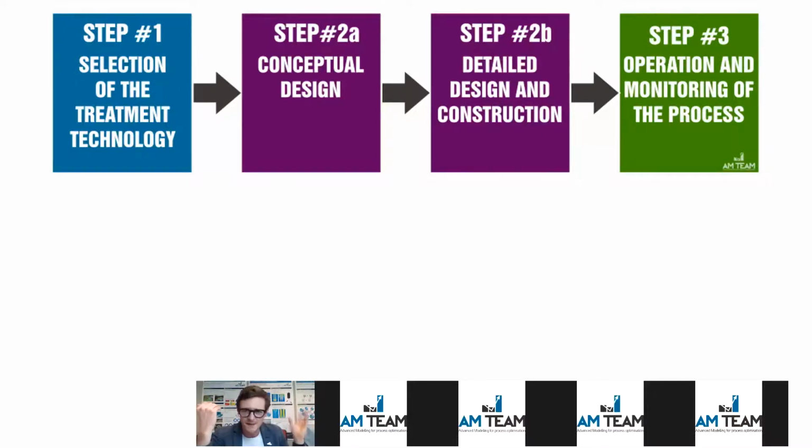Let's run these basic variables through the model and then ask the question, can the model give us back things we cannot measure? So you predict variables you are interested in but cannot measure, based on variables you can measure. Very good examples are the target contaminants, bromate, or CT, including disinfection CT in columns and even side stream systems.